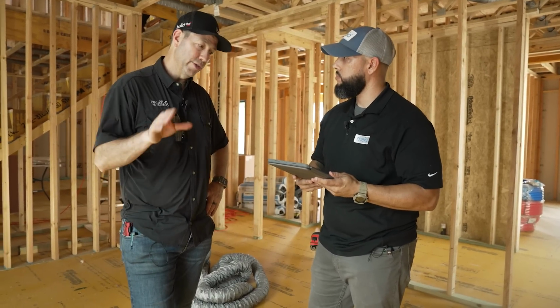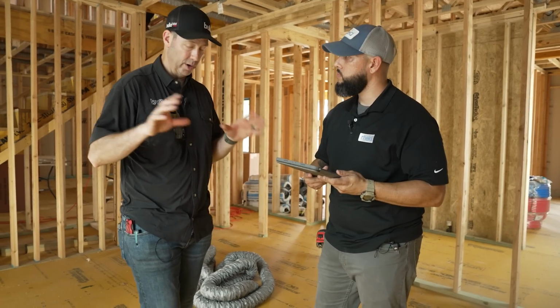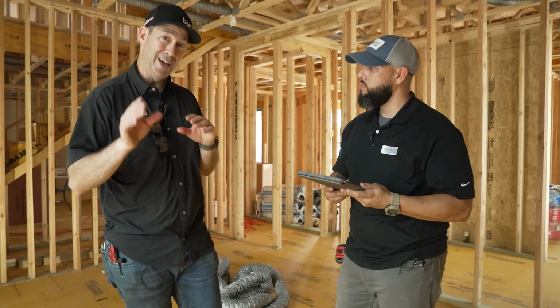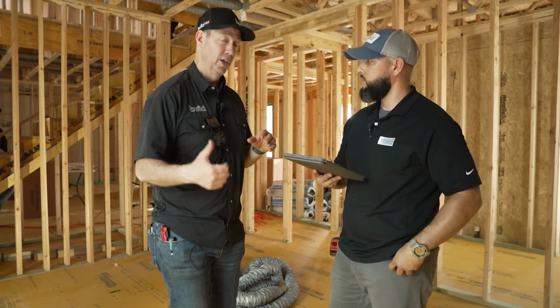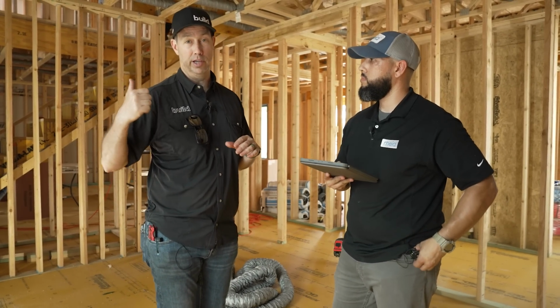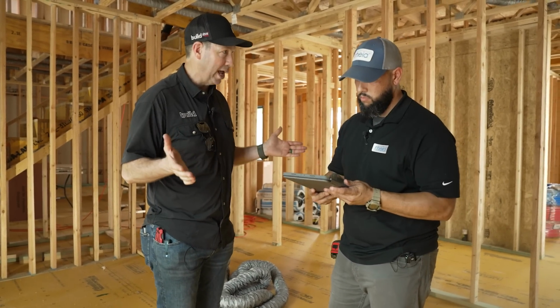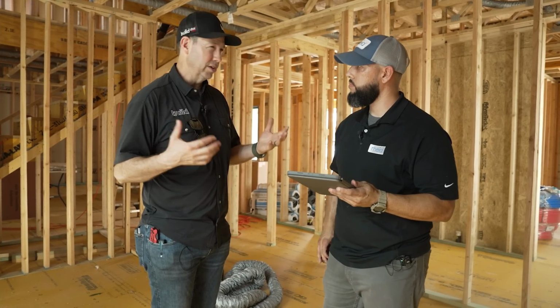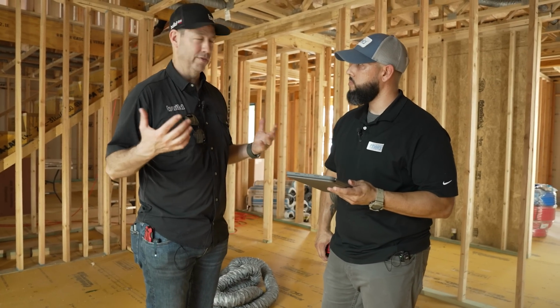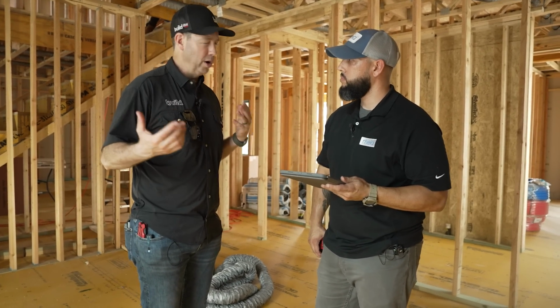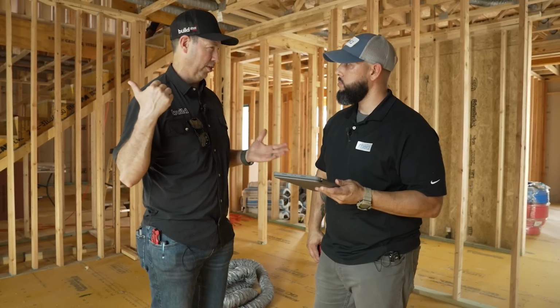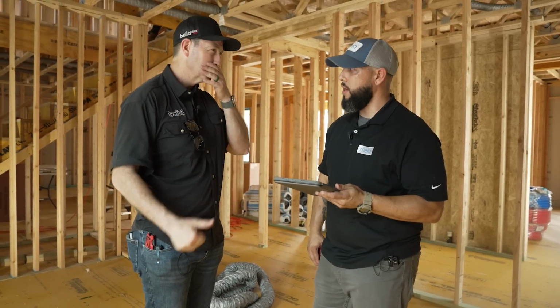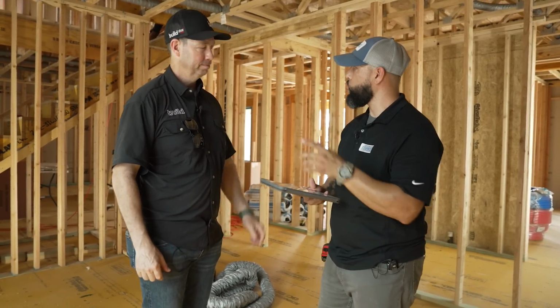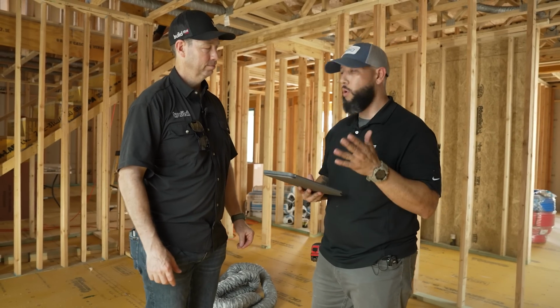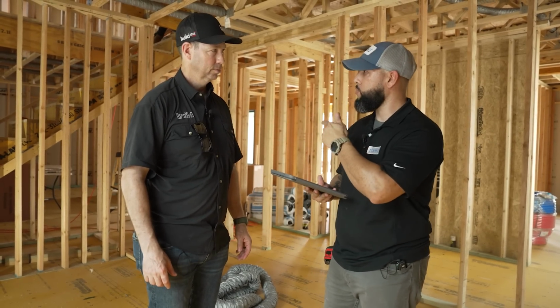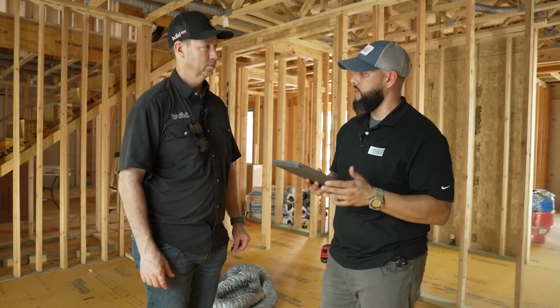Another thing worth mentioning is that this isn't a high pressure or high velocity system, it's standard velocity. Carrier's manual J called for a 2.5 ton unit. I usually think of a ton of AC as around 400 CFM, so this unit is about 1,050 CFM with 21 total supplies. Twenty of those supplies are in the conditioned space, and one is in the attic as a conditioned attic.